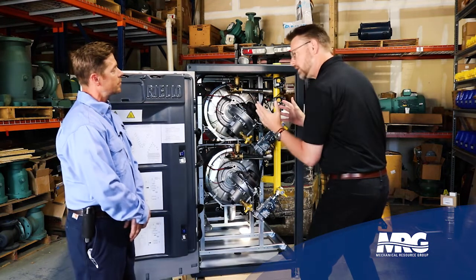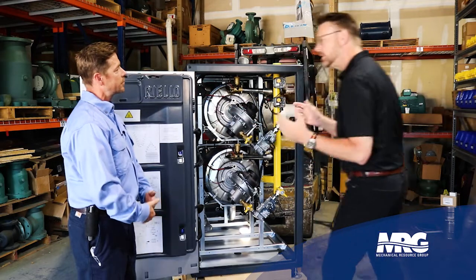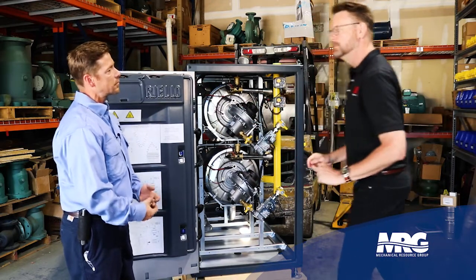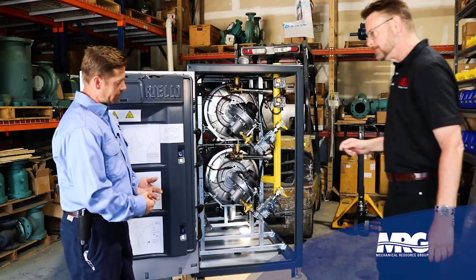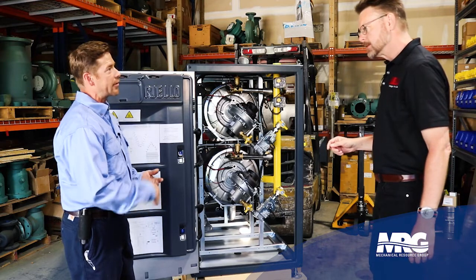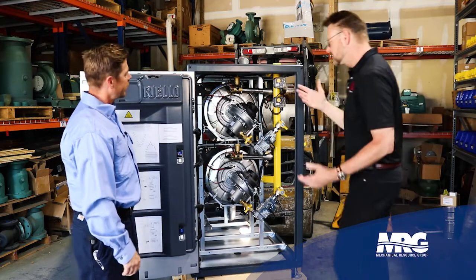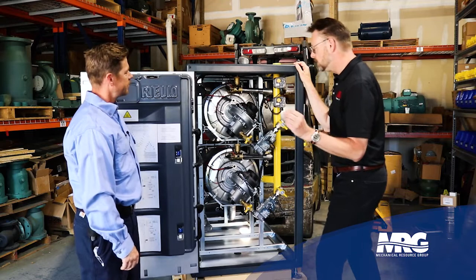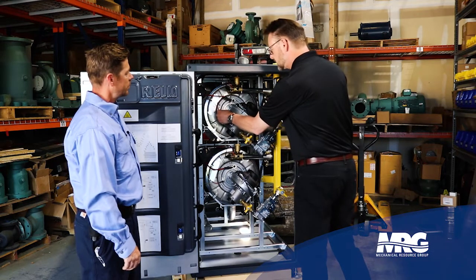So the problem is it won't ignite. Right. What is the problem that you had, the part you had to fix last time? It was an ultraviolet light detector. A flame scanner, flame sensor, yeah. The device that senses the flame once it's established. And in that case, that would be this component here.